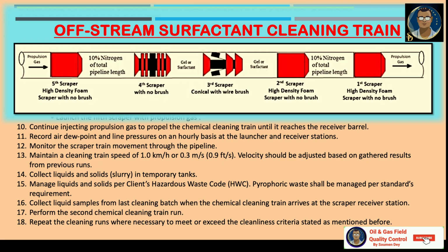Maintain a clean train speed of 1 km per hour, which is converted to 0.3 meter per second or 1 foot per second. Velocity should be adjusted based on the gathered results from the previous runs. Collect liquids and solid slurry in a temporary tank, and manage liquids and solids as per the client's hazardous waste code. Pyrophoric waste shall be managed as per standards requirement.